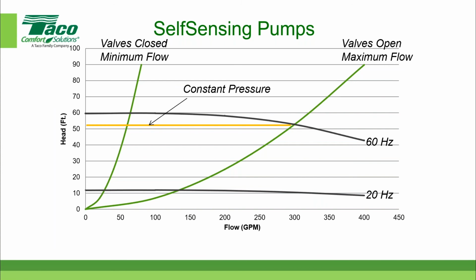You can also, in the field, disable the self-sensing function and land an external signal of 0 to 10 volts, and the pump will operate as a conventional differential pressure pump system. Some people actually do that. They'll buy a self-sensing pump and operate it with an external control. And when they do that, they're using the information that the pump has available in terms of its flow and head, power and speed for a building automation system, but they're not using the self-sensing function. They're almost using the pump as a flow meter so that they can measure the data.